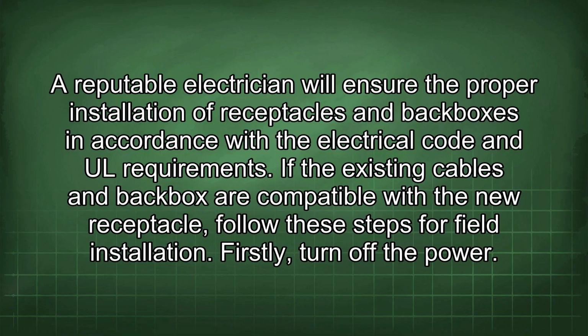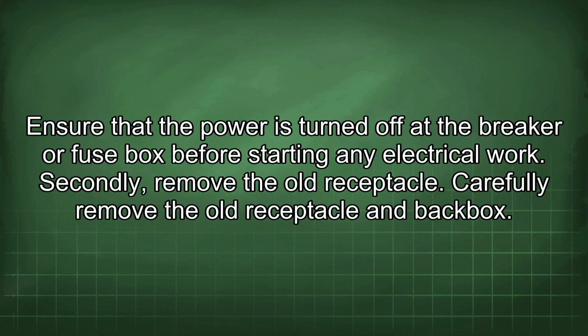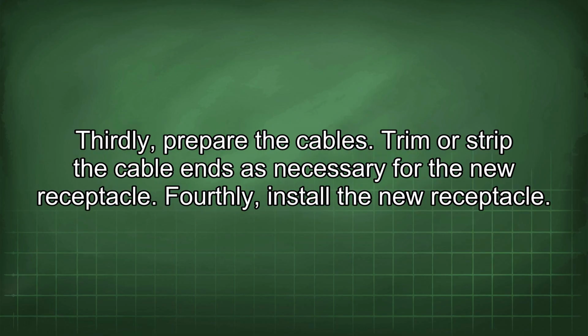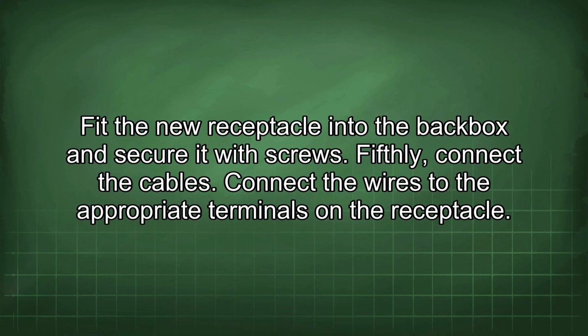Firstly, turn off the power. Ensure that the power is turned off at the breaker or fuse box before starting any electrical work. Secondly, remove the old receptacle. Carefully remove the old receptacle and backbox. Thirdly, prepare the cables. Trim or strip the cable ends as necessary for the new receptacle. Fourthly, install the new receptacle. Fit the new receptacle into the backbox and secure it with screws.